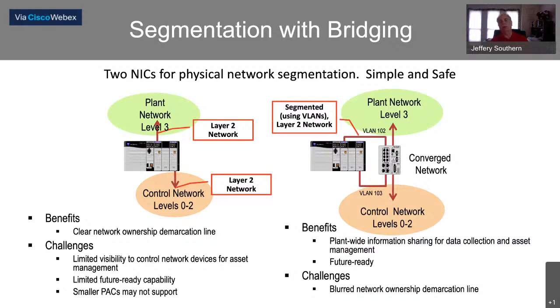So the first one is network segmentation with bridging, and it's kind of what you would expect. The plant network comes down and polls the processor, but it can't go out another network card and start messing around with devices on that second network - that might be your drives and I/O. So you form a physical separation between the two, which is typically what's called a bridge.